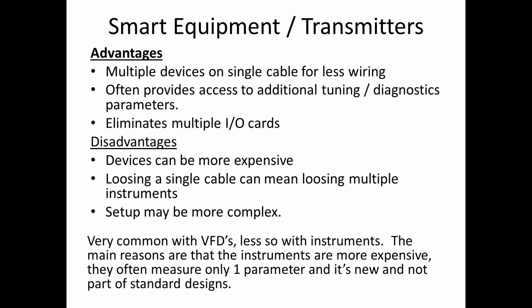The major disadvantage, I think, though, is that if you lose a single cable, you might lose multiple instruments. So that's something you need to consider very carefully and find out what the chances are of losing that cable and what to do in that case. It's very common nowadays for PLCs to have this smart equipment in there. Less so with the instruments. However, I've seen more and more instruments becoming capable of having some of this smart technology.